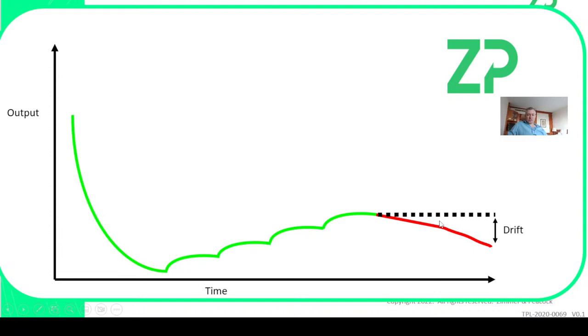Something that's never talked about or asked about is drift. Biosensors and in vitro diagnostics are interesting because they're in contact with the sample — they're intrinsically attached to the sample. So we have a lot more problems with drift. For example, a temperature sensor is often very isolated from the sample so drift is less of a problem. But if you put a biosensor in blood, the signal will drift — blood itself is changing, blood is active.